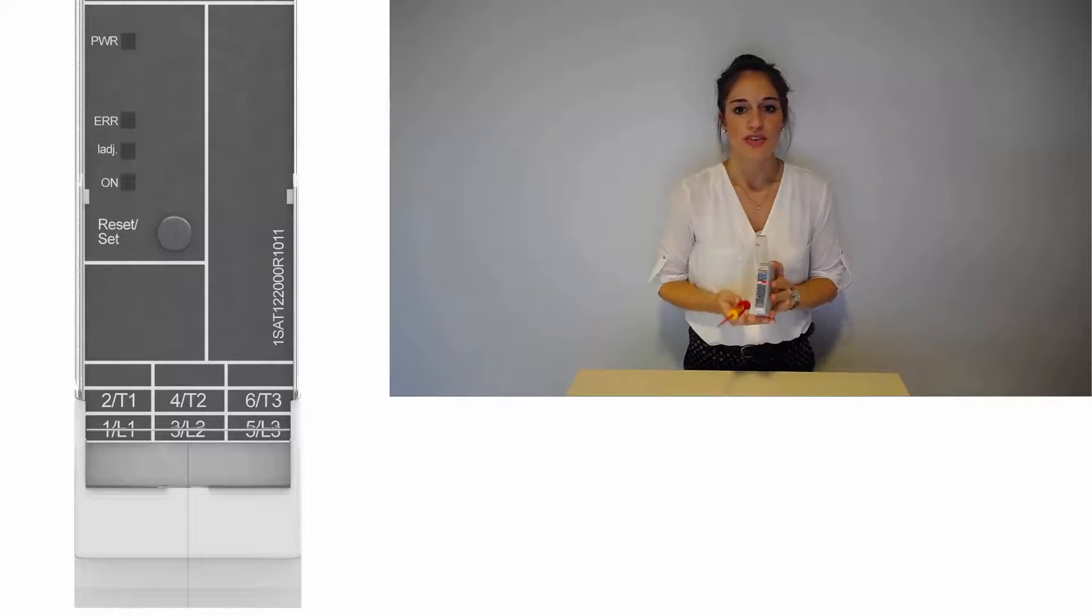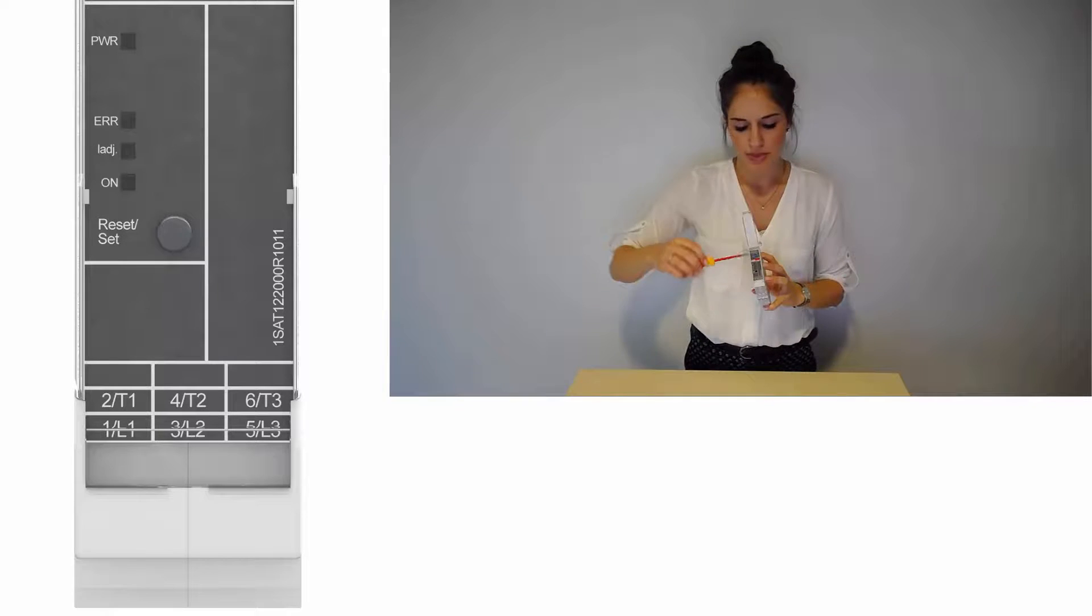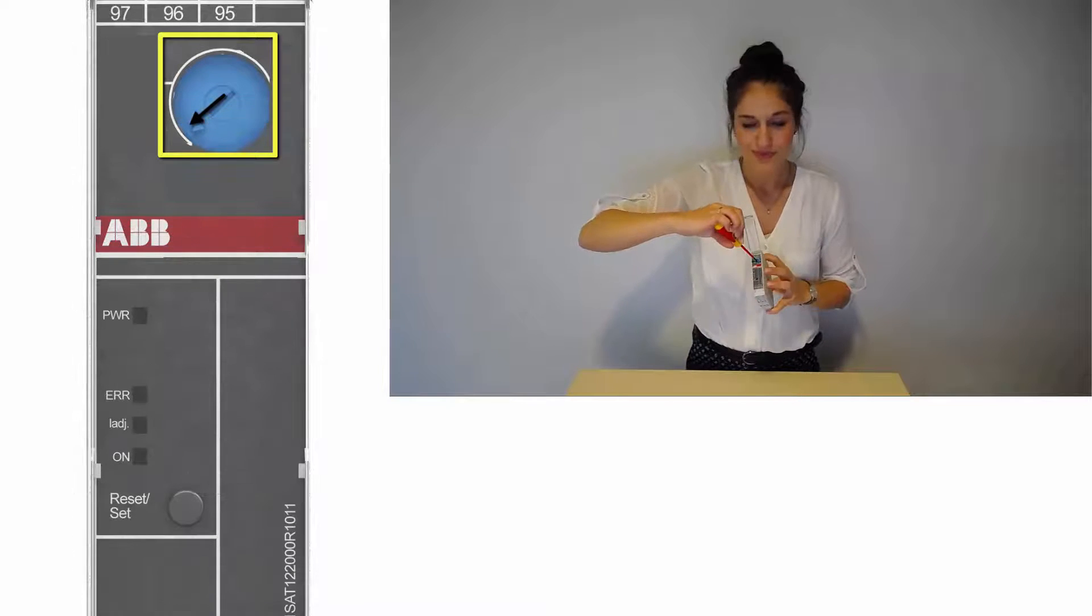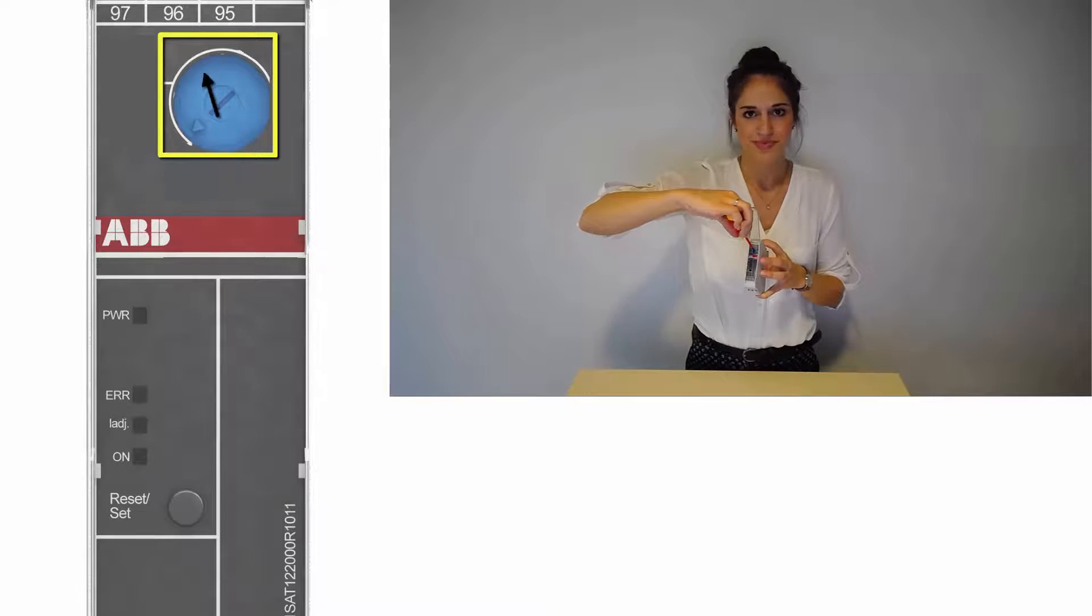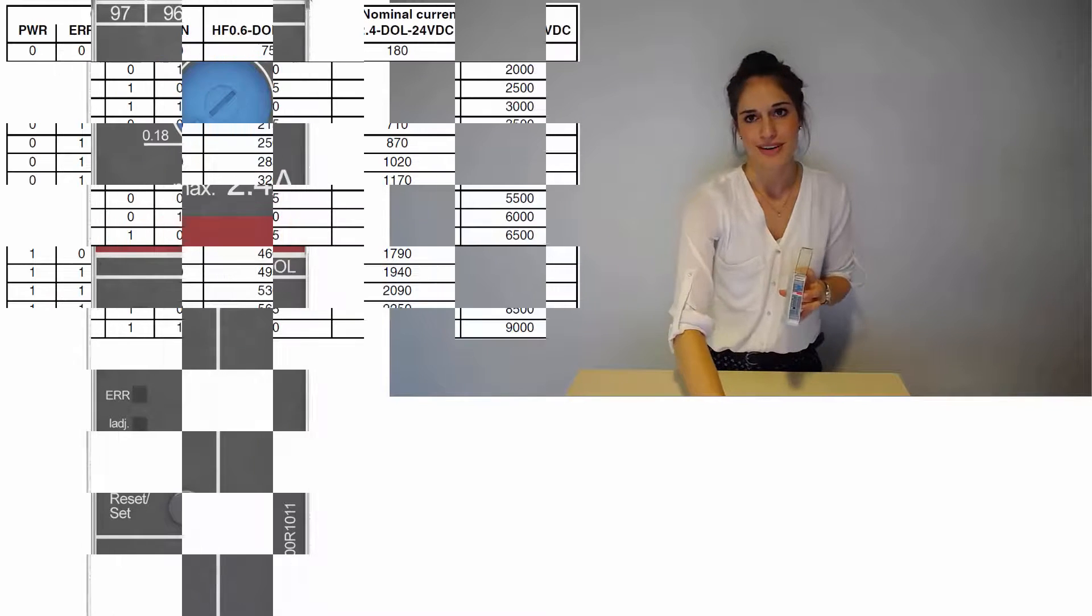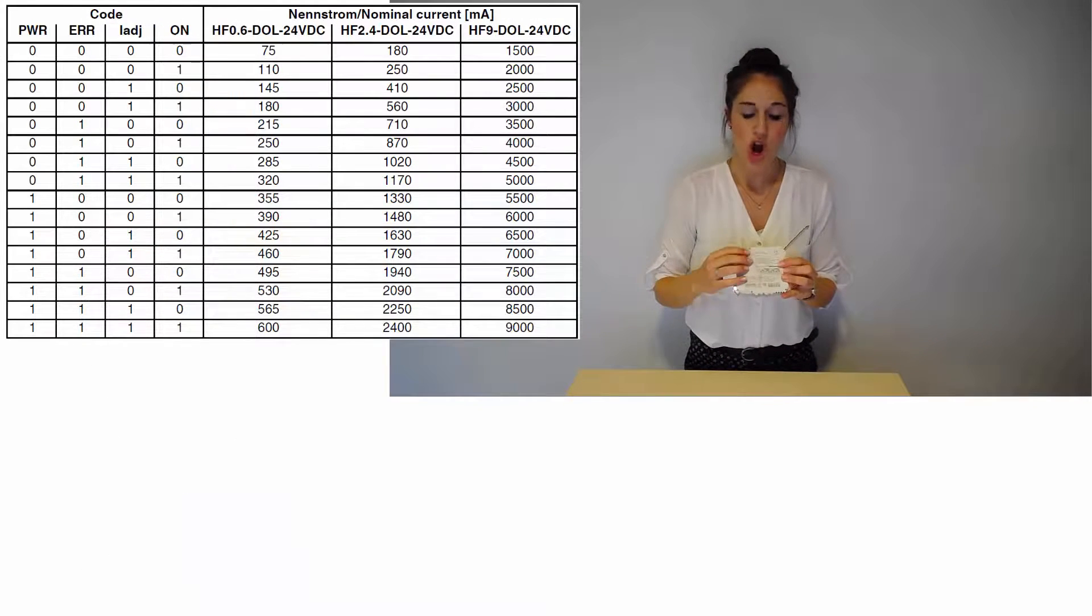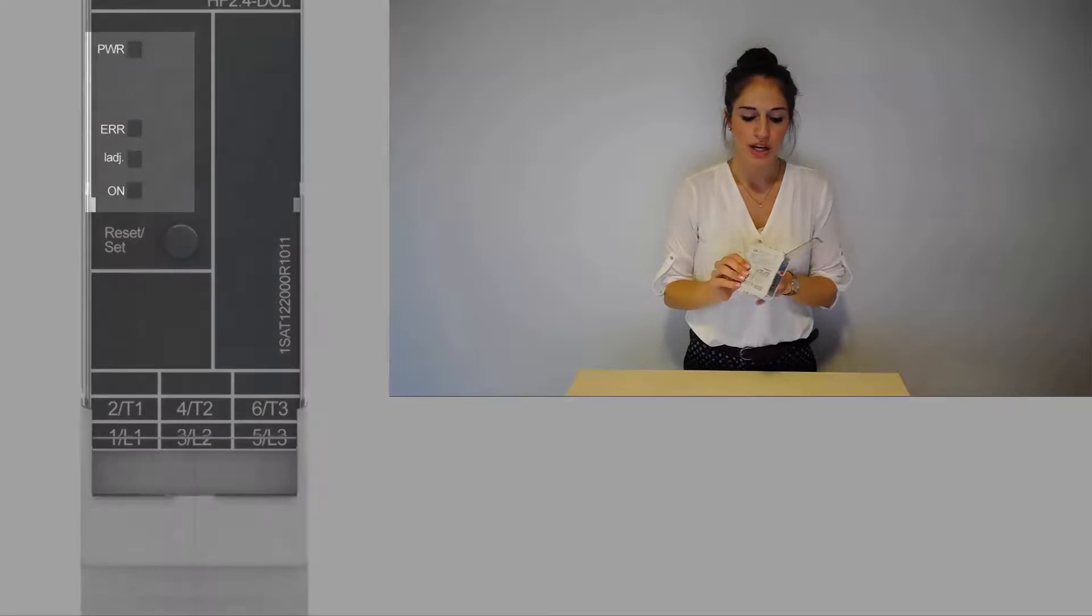Set the nominal current with the 240 degree potentiometer. The nominal current is specified in 16 stages as shown on the device and in the manual. The four LEDs show the set current.